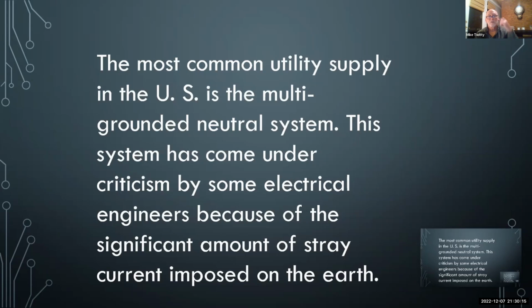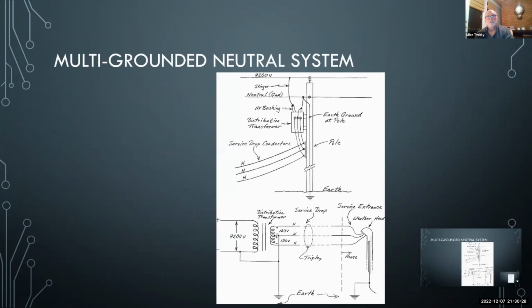This is the most common utility supply in the U.S., a multi-grounded neutral system, and it comes under criticism because they're putting energy in the earth at every house at the pole. Here's a little schematic of it. Here's the transformer on the pole. It's grounded at the pole.